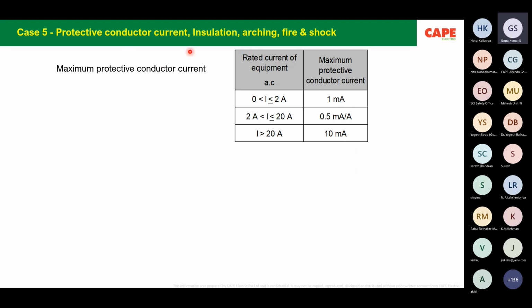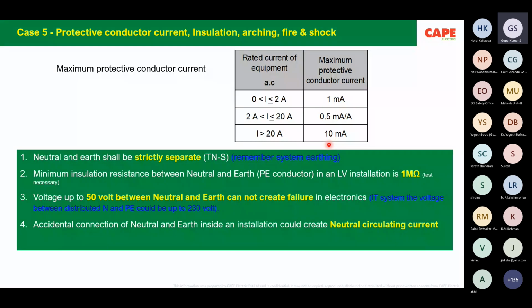But in the new standard, the maximum allowed protective conductor current is very clearly written. If there is an insulation degradation, there is a current flow through the protective conductor, that means through the earth wire. So the maximum allowed protective conductor currents are mentioned. It is easy to follow. You have to follow certain rules very strictly to ensure that the current is less than the allowed protective conductor current. Now, this being probably one of the very important safety measures, there are products called digital earthing systems sold in the market. The manufacturers claim that this is a one-stop solution for all your earthing problems. If you read the catalog of these devices, you will see that this digital earthing or digital grounding system is a product directly from God. That is the impression they try to create.